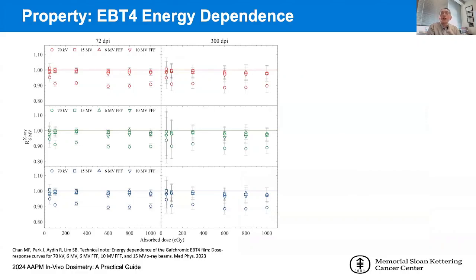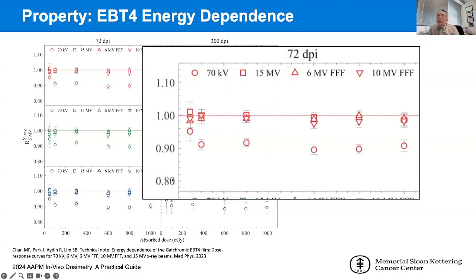So switching over to the energy response, which is quite important in understanding the use of the film. Here is the dose response on the y-axis and the dose range on the x-axis. Here, looking at the dose response relative to an ion chamber system at 6 MV, exposing it at different dose ranges from, I think, around 50 centigray to about 1,000 centigray, and scanning it at 72 DPI and 300 DPI. As you can see, the scanning resolution really doesn't make a huge difference here. So let's just focus on the 72 DPI, which is probably applicable to most applications here.